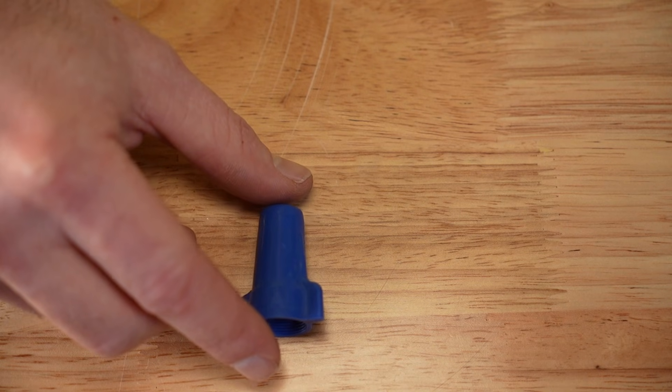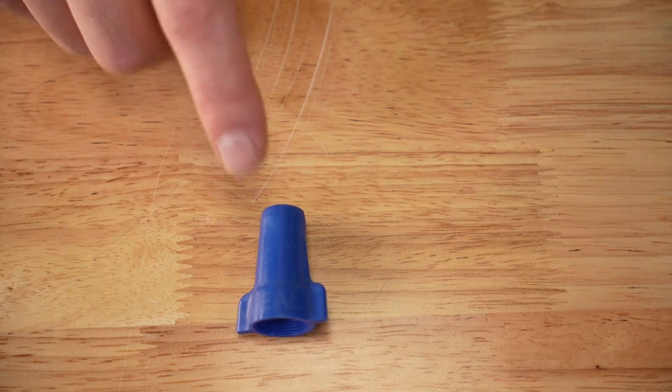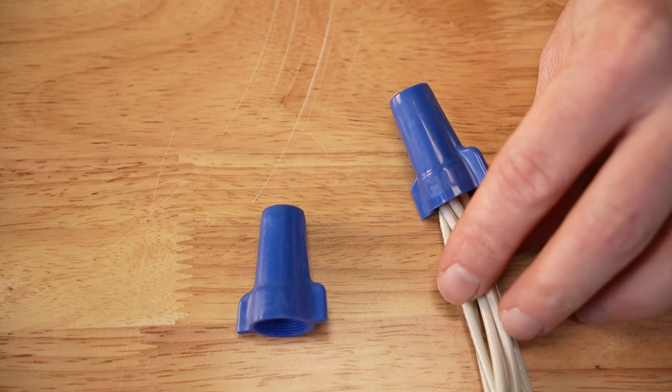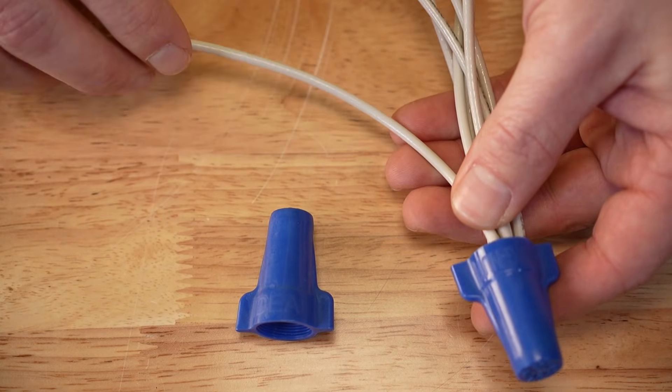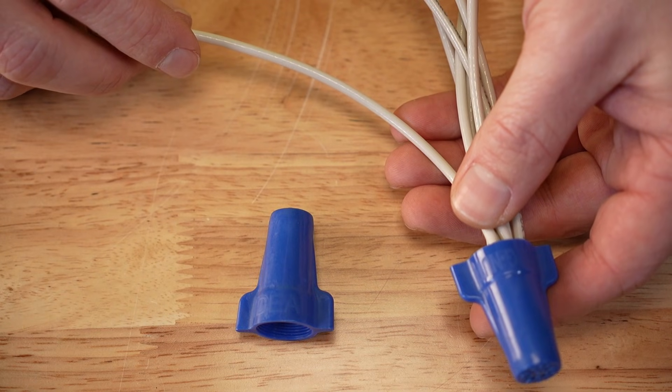These big blue wire nuts are listed for up to six 12 gauge wires, which looks like this. A seventh wire will physically fit, but keep in mind this configuration is not permitted by the manufacturer. There are certainly electricians out there who do this and other unapproved combinations regularly. Just remember that when they do, they are assuming the liability for that connection under their license.